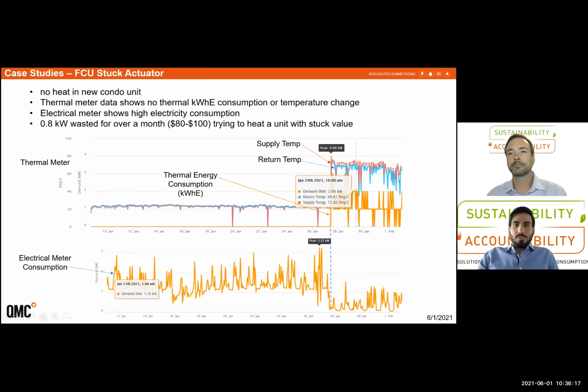So this example is showcasing a cool case study utilizing thermal metering data to analyze a fault within a residential fan coil. The graph in the middle shows supply temperature in red, return temperature in blue, and thermal energy demand in orange from the thermal meter within the fan coil. And the graph on the bottom shows simultaneous demand from the hydro meter for the same suite. The occupant in this suite was complaining about heating issues, and looking at the meter data and the graphs in the middle, we could easily diagnose the cause as a stuck actuated control valve, which is a common occurrence in residential fan coils and heat pumps.